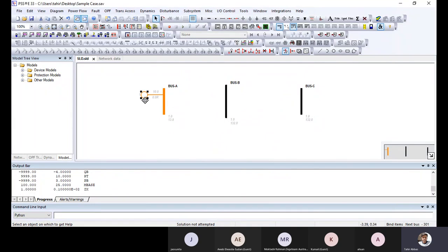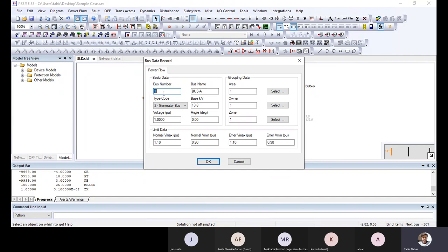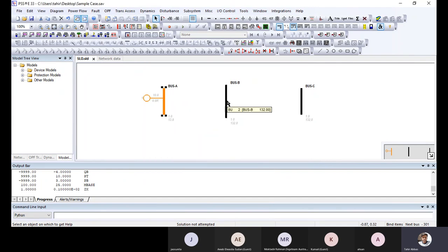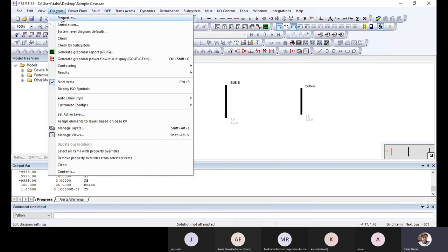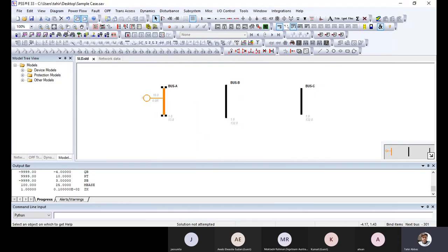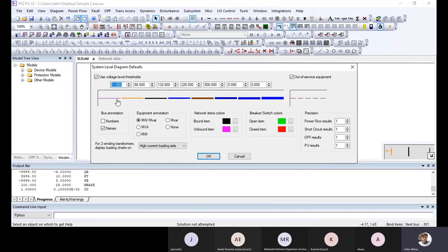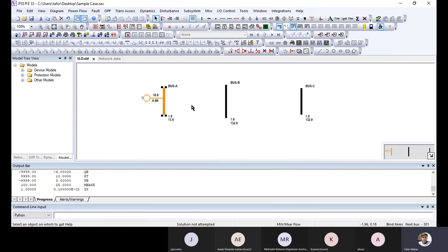Then, pressing escape, here you can see that the generator is available. Next, because the voltage is 13.8 kV and the next voltage is 132 kV, why are there different colors here? I will show you that there are different annotations I have already defined here in the system default level. You can see for 11 kV this color, for less than 66 kV this color. So there are different voltage threshold levels, and different system level diagrams are defined.